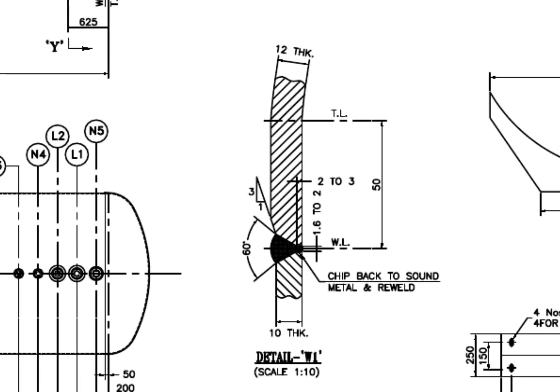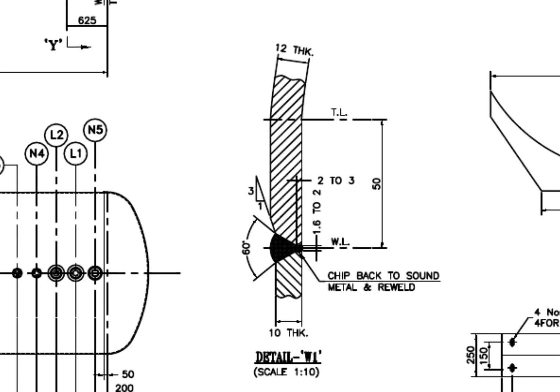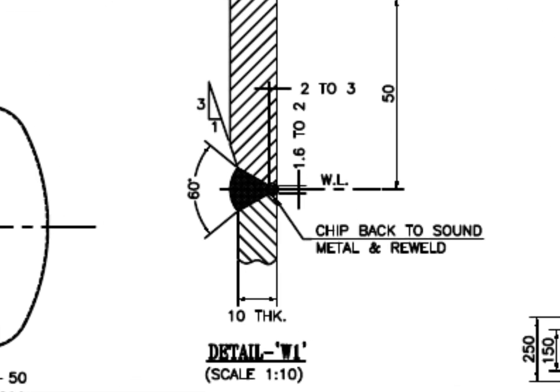Detail W1. This is the welding detail of the dish to shell joint. The thickness of the shell is 10 mm and the dish end thickness is 12 mm. 1 is to 3 bevel is prepared on the dish end edge and ID matched the thickness with the shell.